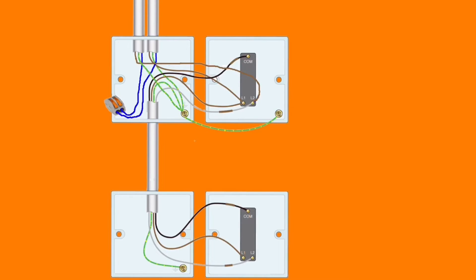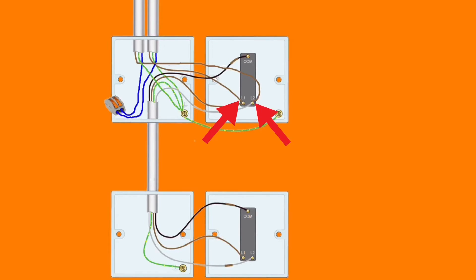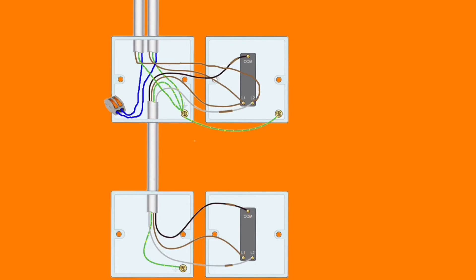Our two brown conductors were previously in common and L1. They've now been reattached to a two-way switch going in L1 and L2. We've introduced the three core cable which connects the two-way switch at the top with a new two-way switch in position.